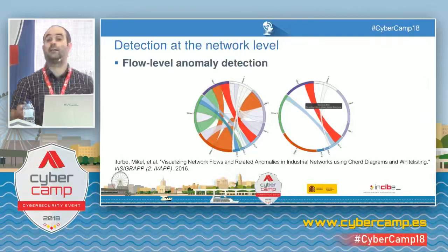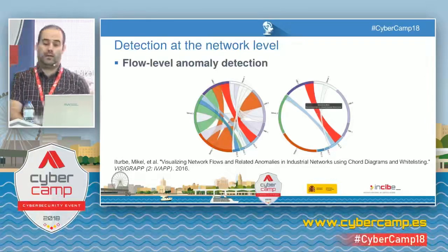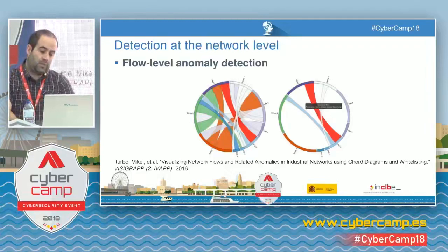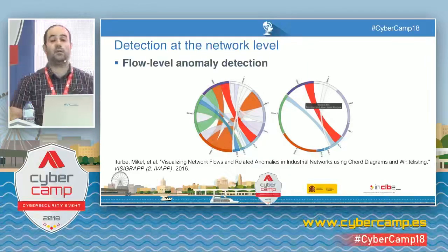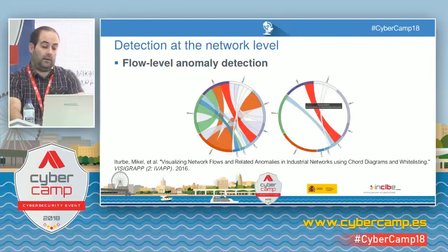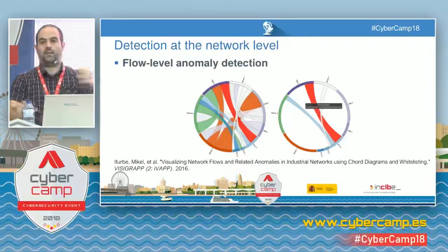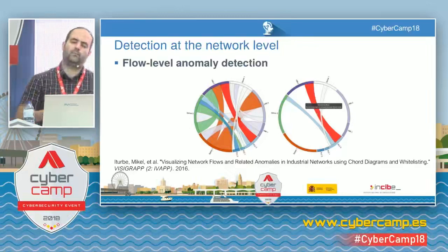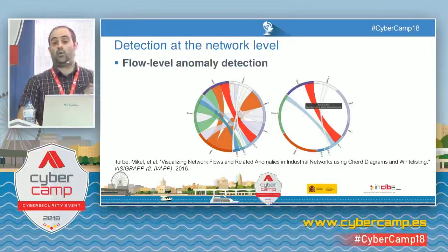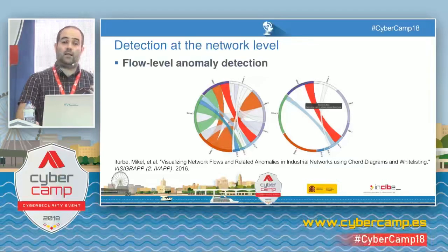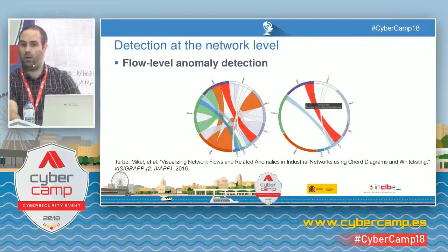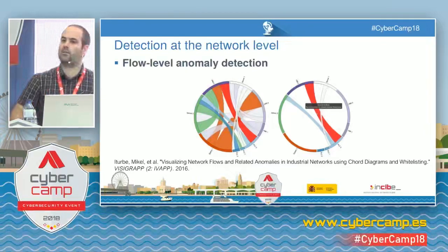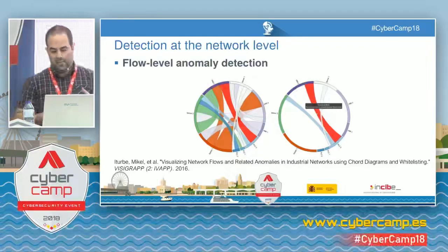See the flow between HMI and PLC where we should not have any traffic, and we see that it is red. This was done with a car painting line. It is a real example. And as a reference, you will see some other use cases where we detect DoS. And it is not just the existence of abnormal flows or the non-existence of a network flow. If a PLC is offline, we need to know why, because that's also important. We don't know what's going on with the process. So that's it.